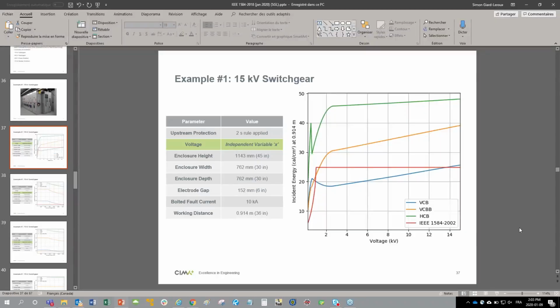Said the incident energy, for less than 2 kiloamps and 240 volts, what stickers do you put on? I think you explained that. But since there's no category 0 or no indication of what to do for less than 1.2 calories, if I calculate 1.2 calories or less, what should my sticker say? If I calculated incident energy. In the case that you're below 240 and below 2K? No. So say I'm 480, but I've calculated less than 1.2 calories exposure. So you should put that energy on the label? That's the way I feel about it.